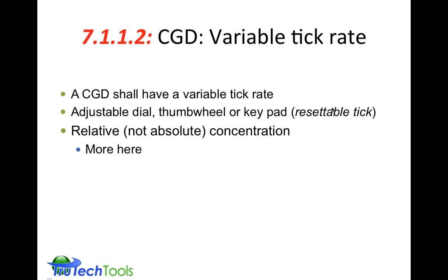For the gas leak detection part of its job, it must be measuring relative, not absolute concentration. In other words, detecting more here and less there. So it's in the leak detection mode. And there's actually a couple modes for the combustible gas detector we should be aware of.